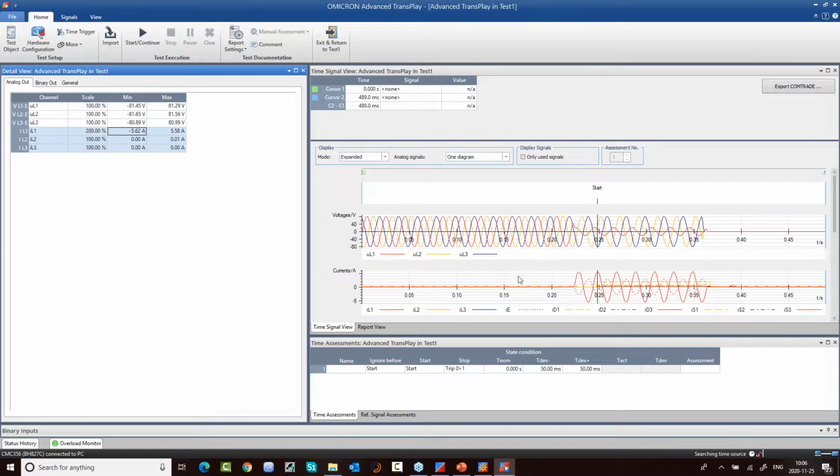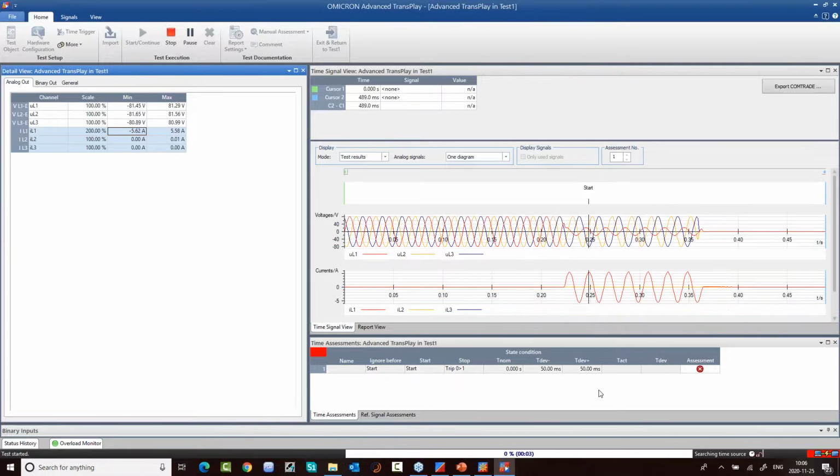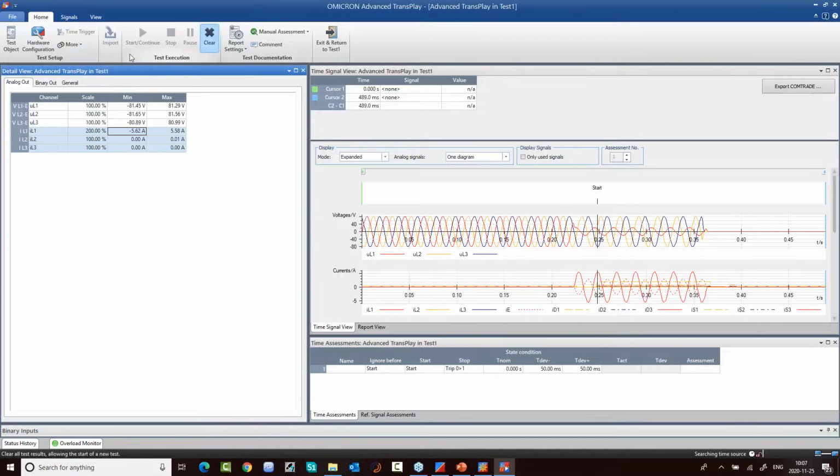This also can give us access to the analog to increase or decrease it. For the voltage and current, you can easily do it. In our example, it doesn't matter because it is differential protection, and we didn't get a trip. Maybe CT supervision started or something. Okay, just 1 minute. Okay, let's start again. See.